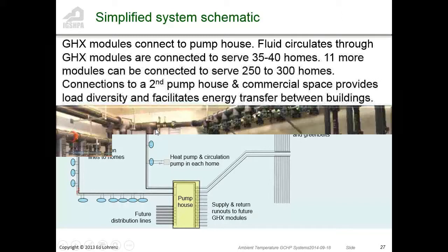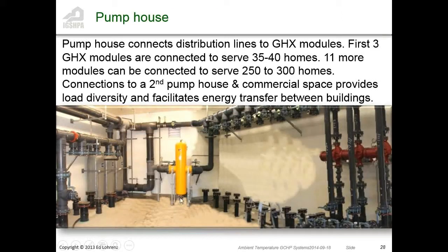So this is the inside of the pump house. The only pumping in here right now, at this point there are only 3 heat exchanger modules connected to it. There's a pump on each one, and those pumps come on based on the temperature inside this common header. This is where the distribution lines are going, though this one isn't connected yet.